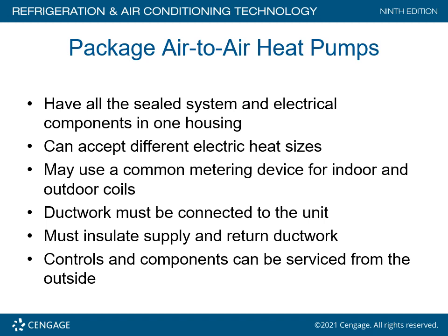The nice thing about a package heat pump, everything is central to the package unit. I've worked on a lot of package units in my career. Package heat pump units tend to be very long-lasting, a little bit forgiving as far as temperature extremes. The biggest problem that I find with the package units is improper ductwork connections. I've had reversing valves go bad in these things. Not very often, thank goodness. But for the long haul, these package unit heat pumps are a very reliable method of delivering heating and cooling to, like, say, an office as an example.